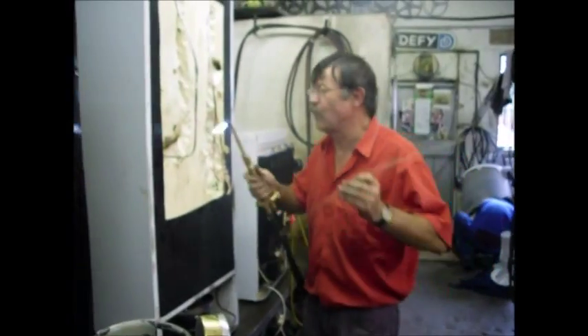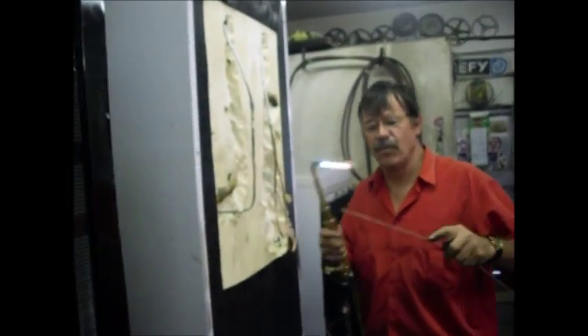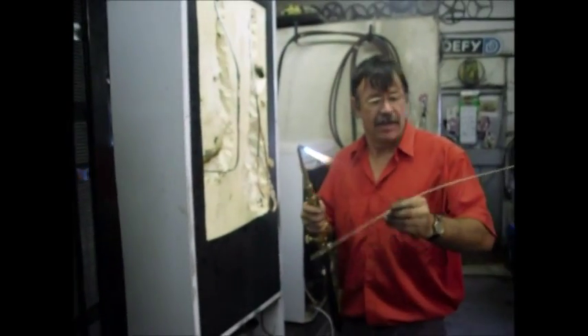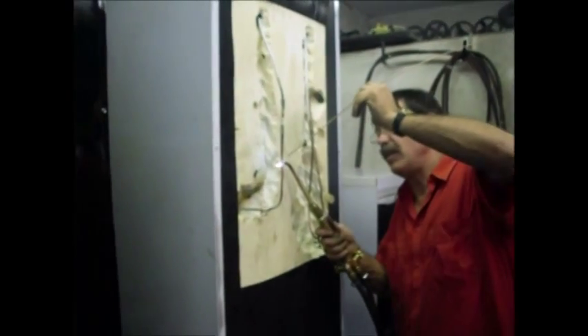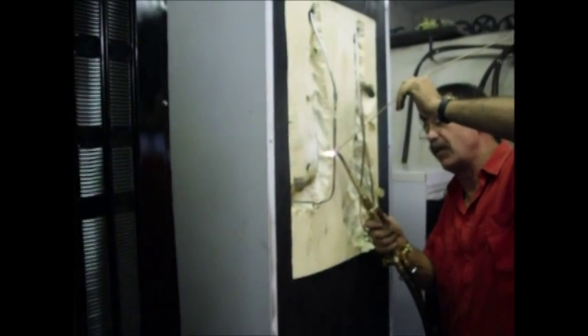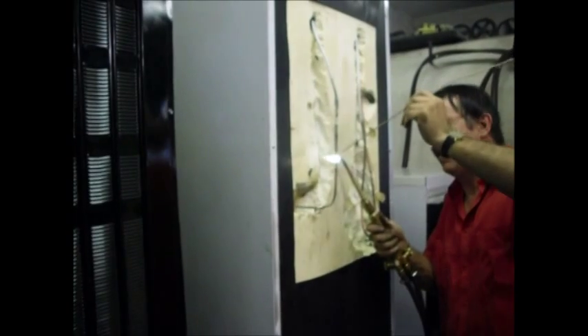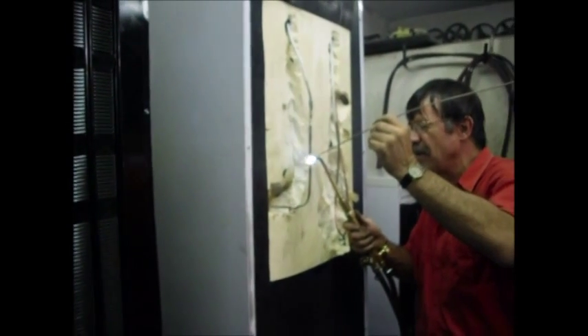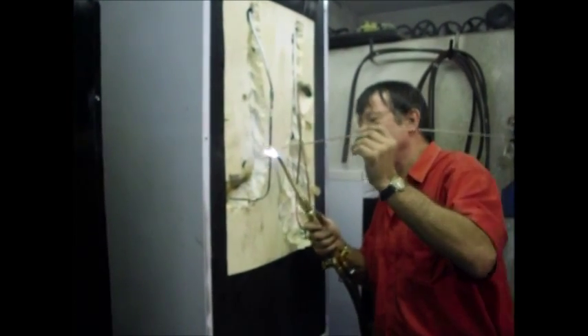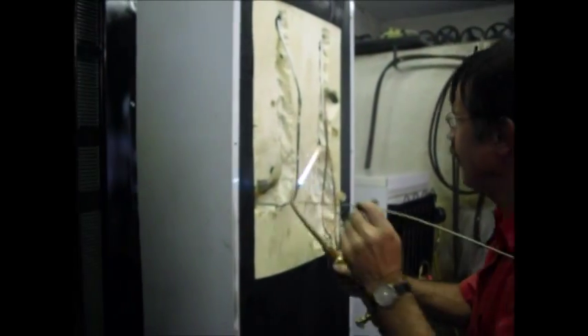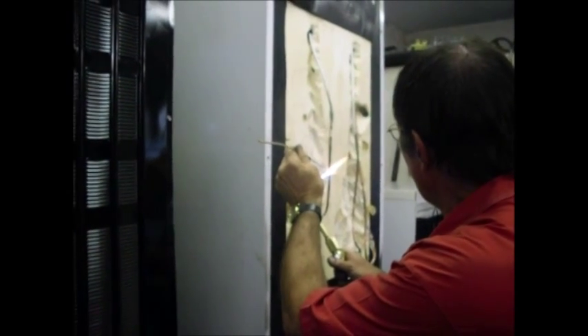The copper to copper which is done with this rod is called silver alloy. You don't need any flux and it melts very easily, it flows very nicely and has a perfect weld that will never leak if it's done properly.